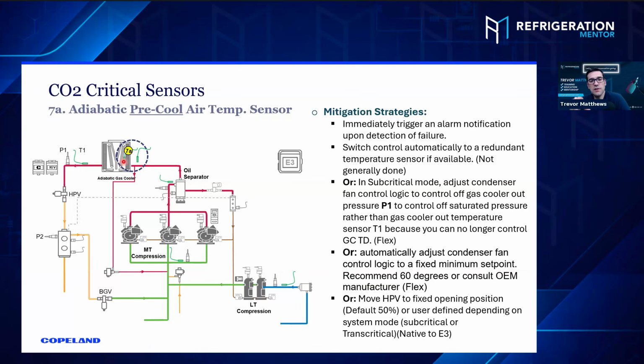Yeah, that's a big thing, right? Most of the systems here in Canada aren't adiabatic, like we talked about earlier. But these sensors are super important. Two days ago here in Ontario it was like 33, 34 degrees. Adiabatic would have been perfect because you would not have gone into transcritical on those days, since you're only 4 degrees out and the humidity wasn't super high. We would probably have been able to keep that system in subcritical that whole time. But if that sensor failed, we probably would have gone into transcritical on those days.